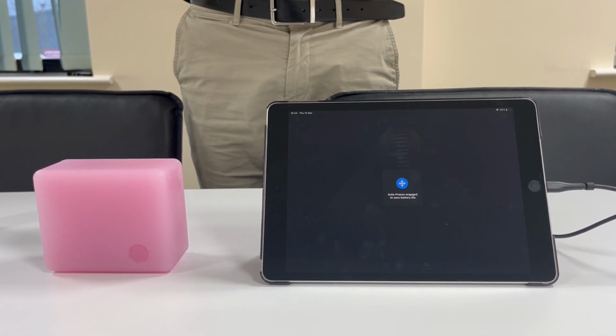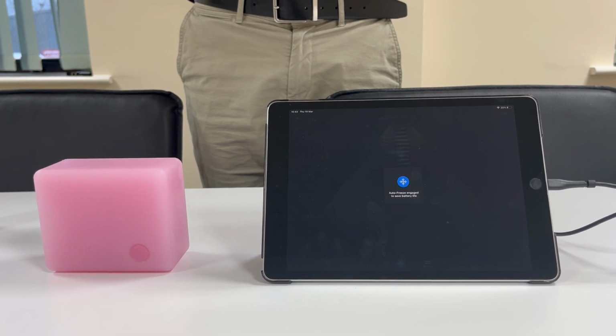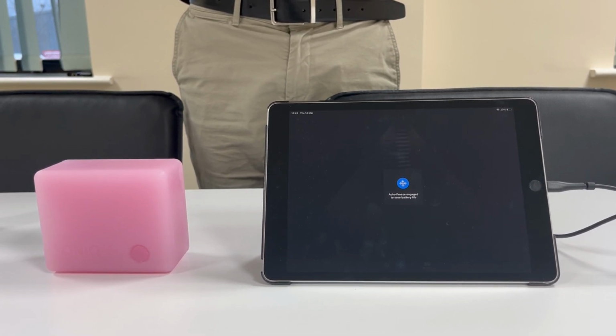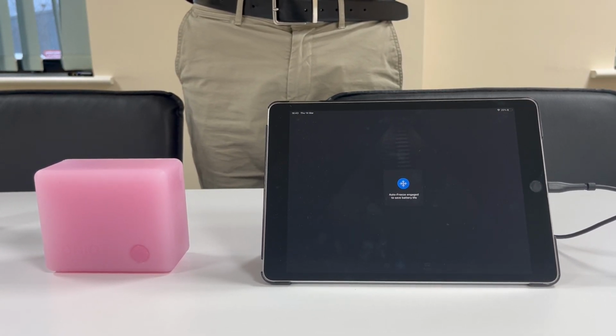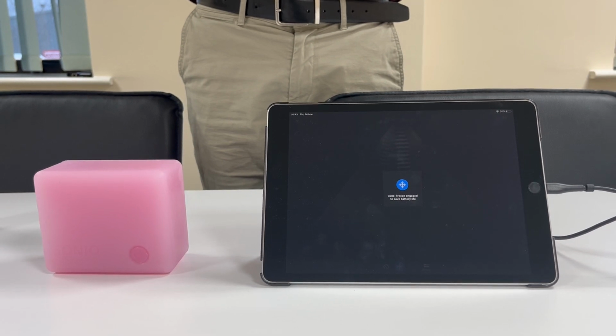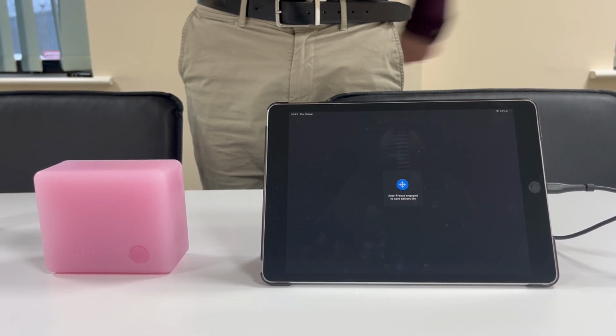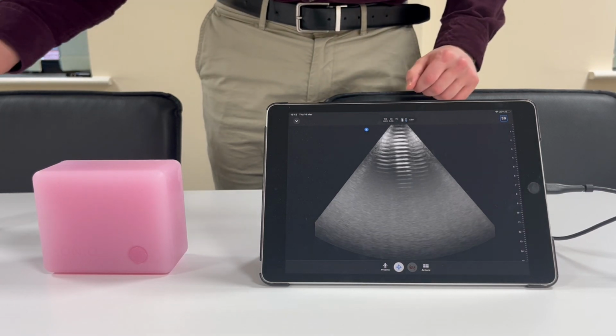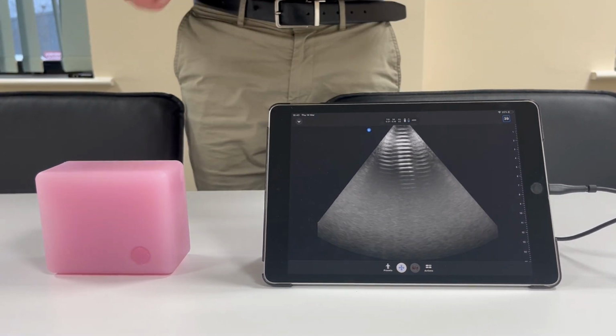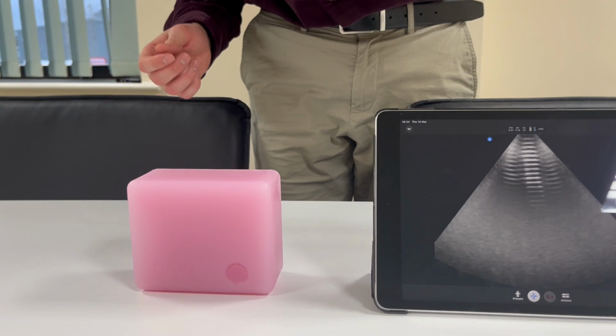To test for uniformity with the SonIQ Uniformity ultrasound phantom, first select the appropriate settings on your ultrasound system. Preferably, this would be a uniformity setting. Once ready, generously apply ultrasound gel to the surface of the phantom.